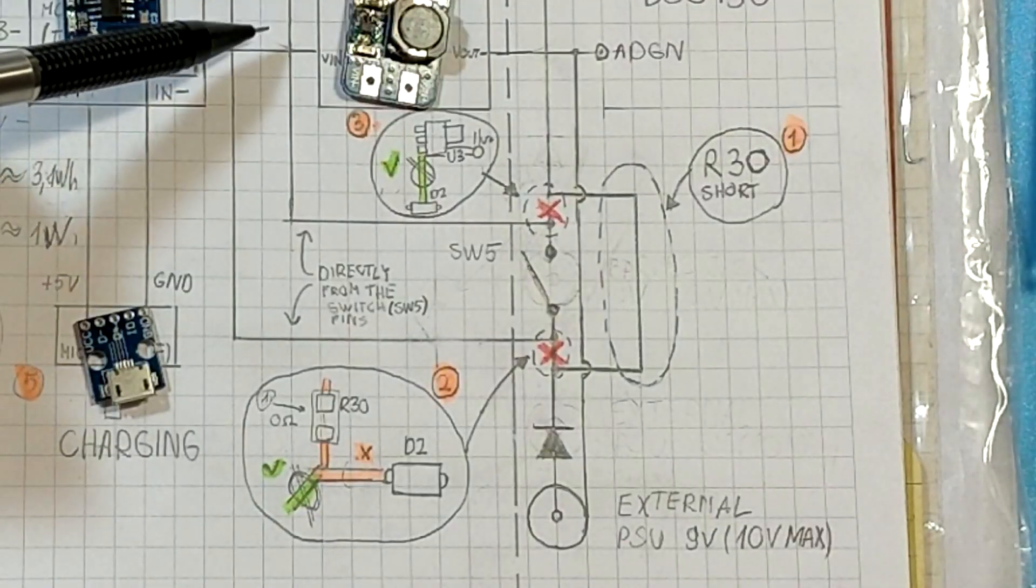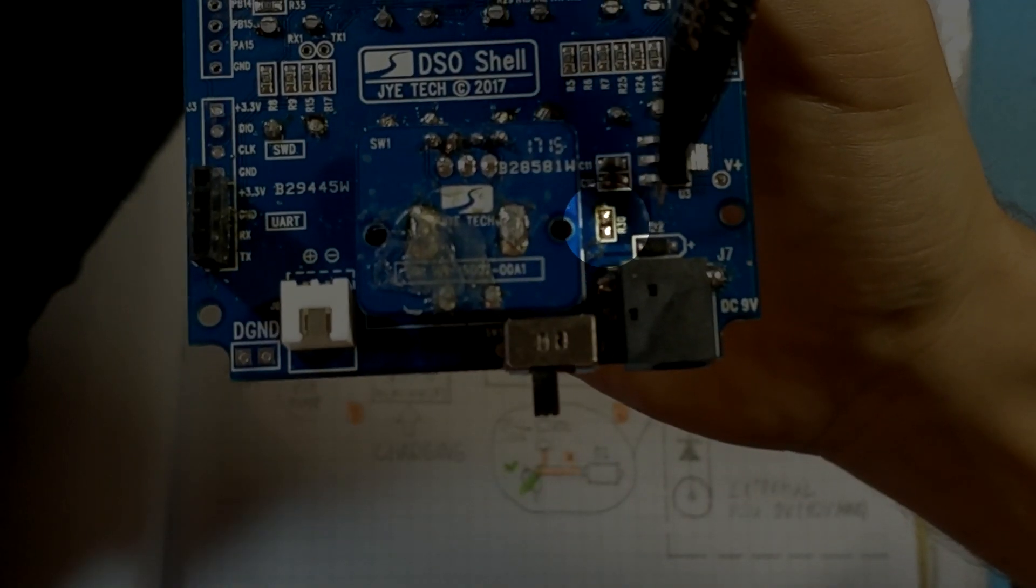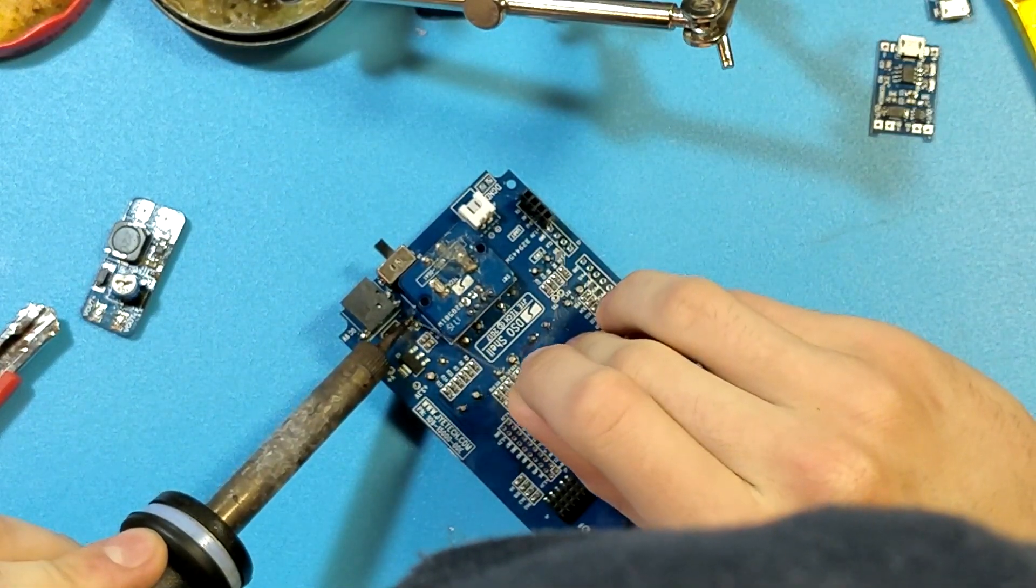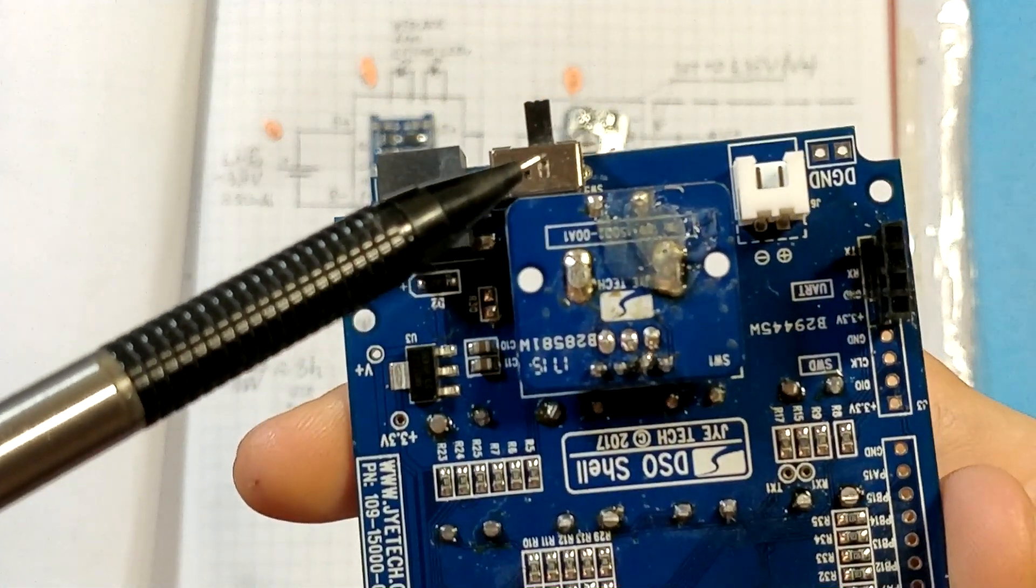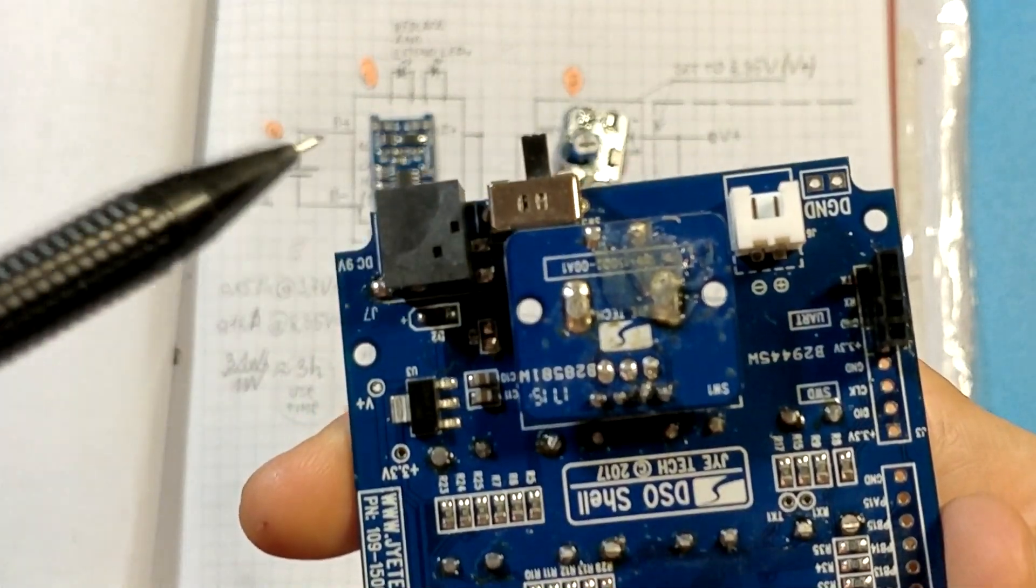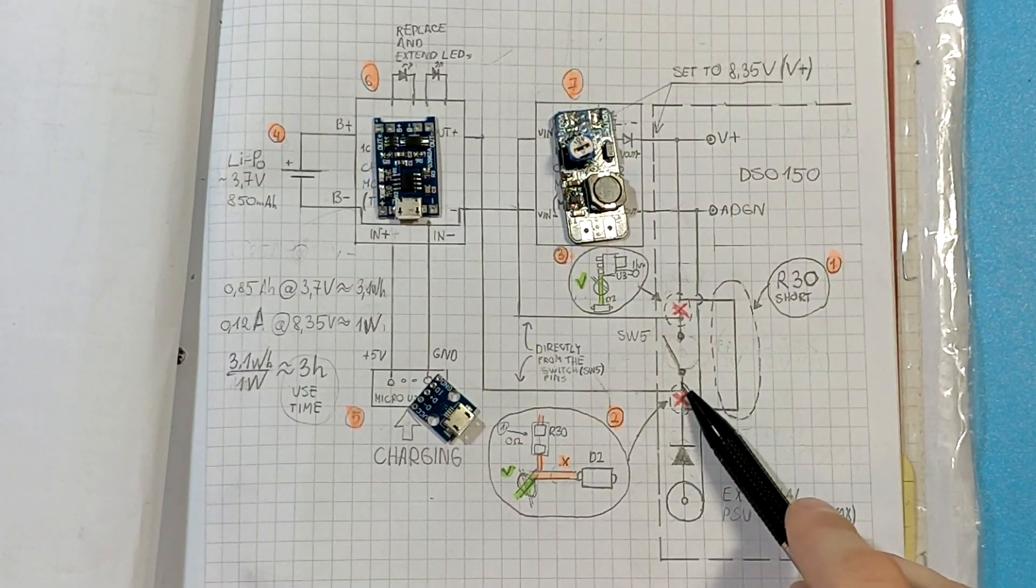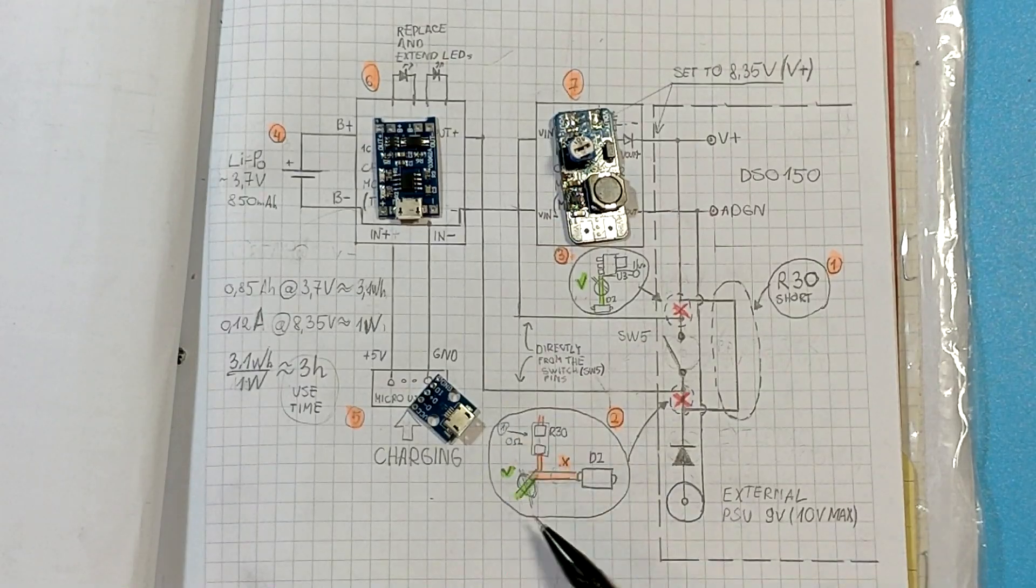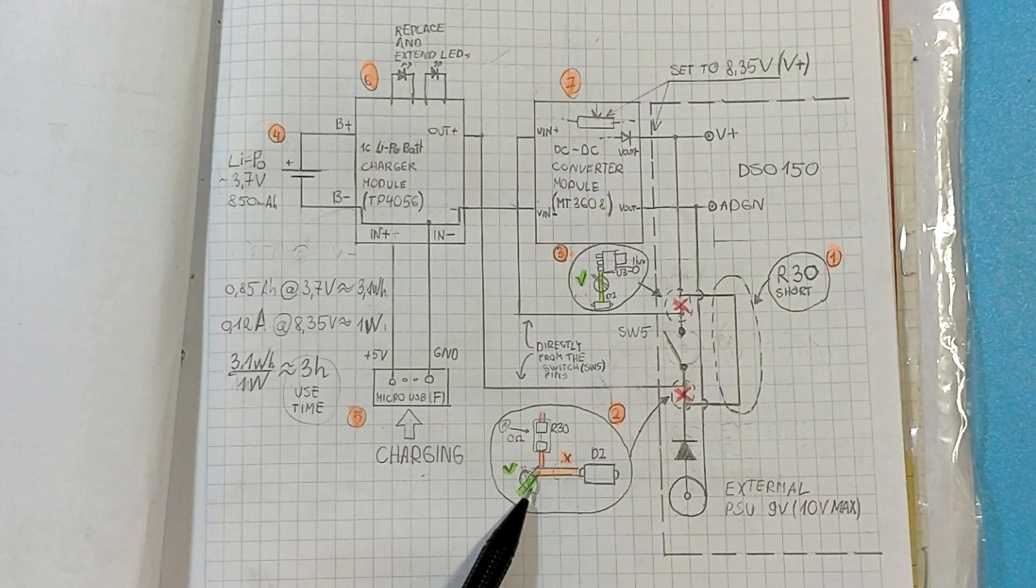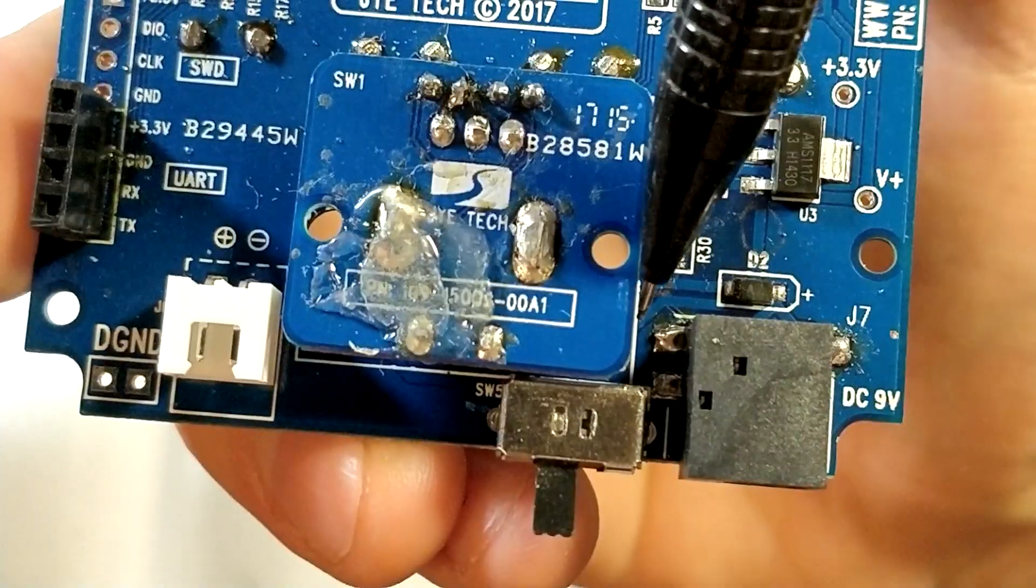First step is to short unmounted R30 pads on digital board. This bypasses the switch SW5. To electrically disconnect the switch from digital board we have to cut out a trace shown on the second step. I've drawn a fragment of digital board physically located here. The green colored part needs to be disconnected.